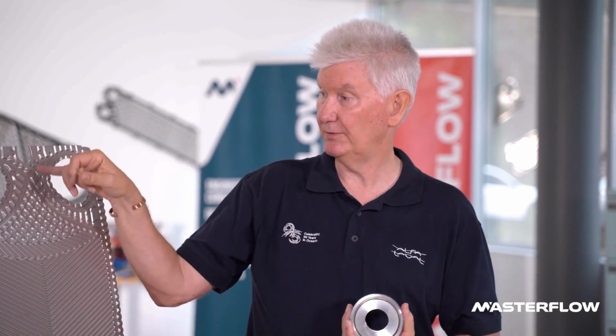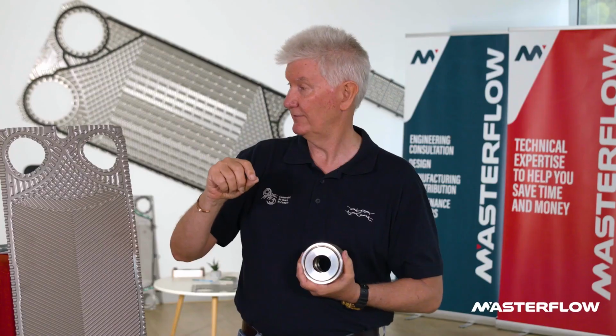They're very weak up in this area, talking about 0.5 to 0.6 millimeters. On our bigger heat exchangers, we actually weld a hanger there to strengthen that plate. You'll see a spot welded plate, top and bottom, and that adds extra strength for the large, heavy plates to improve their alignment.